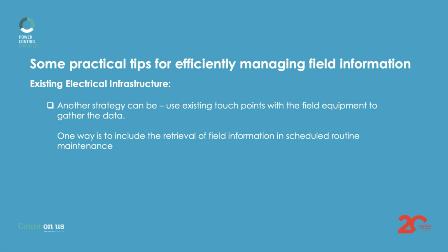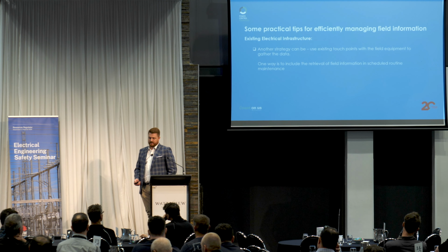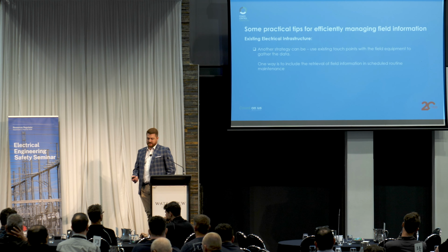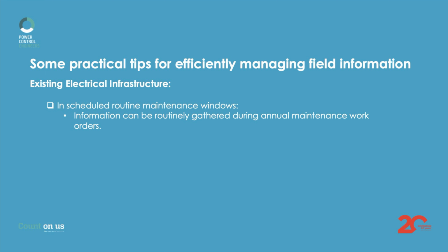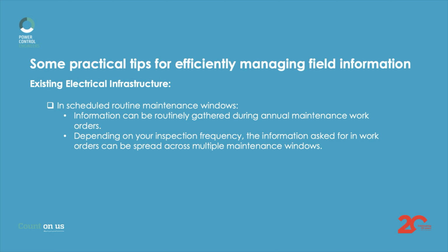Another strategy is that you can use existing touch points with the field equipment to gather the data. So one way to do this is to include the retrieval of field information in scheduled routine maintenance. In scheduled routine maintenance windows, information can be routinely gathered, by putting the information that needs to be gathered on work orders. Depending on your inspection frequency, the information asked for on work orders can be spread across multiple maintenance windows.